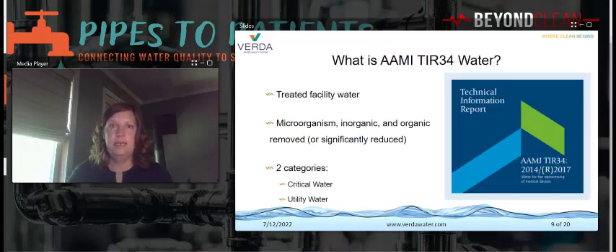So what is AAMI TIR 34 water? It's clear that water quality is important. It's important for equipment performance and uptime, instrument life. It's important for patient care. It's so important that AAMI, the Association for Advancement of Medical Instrumentation, created a technical information report, TIR, defining categories of quality water needed for medical device processing, how to generate it, how to set up a quality program to monitor and maintain it.